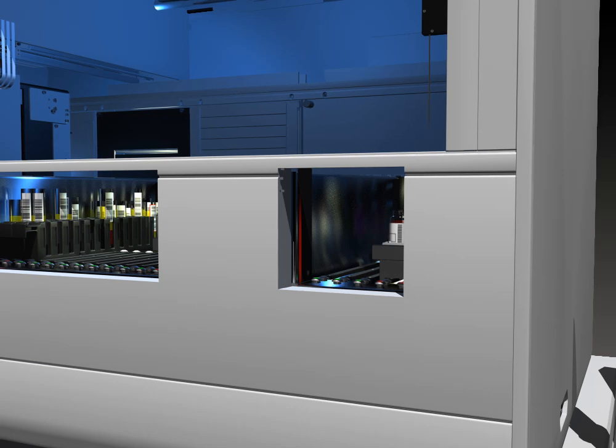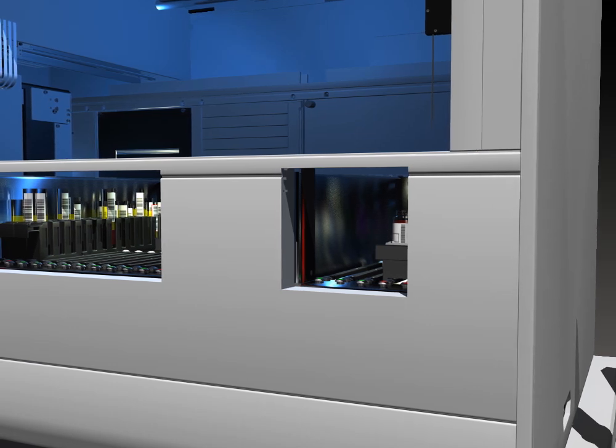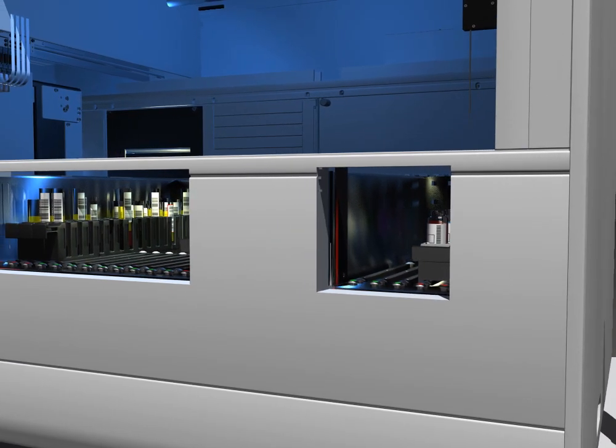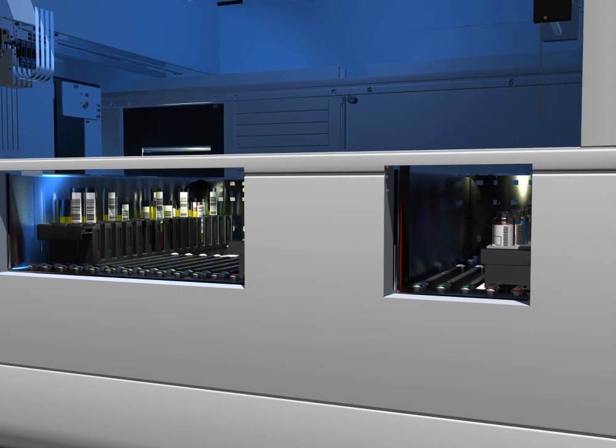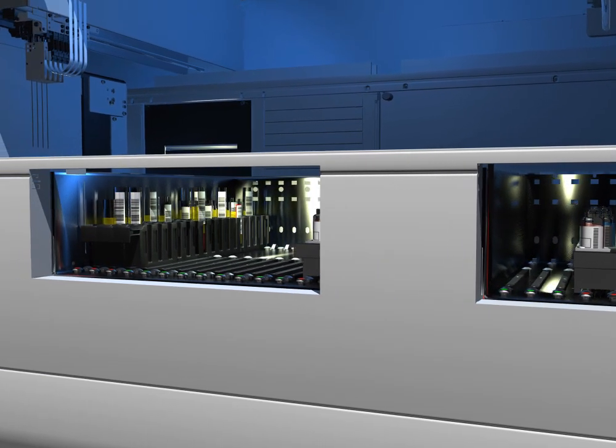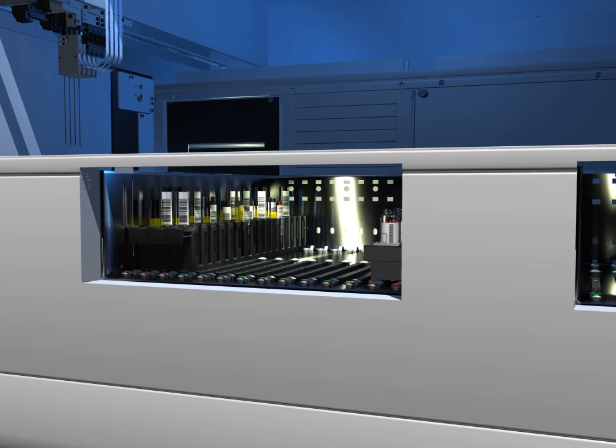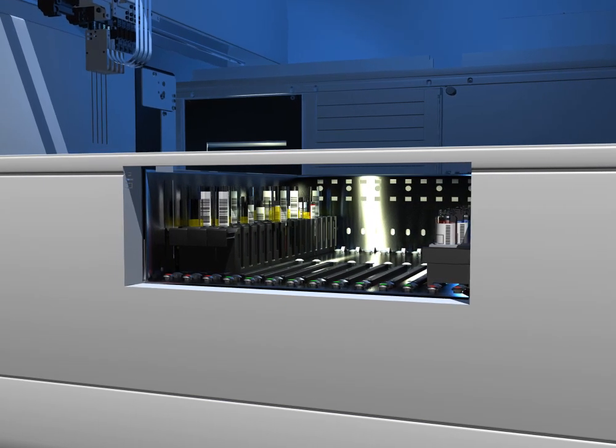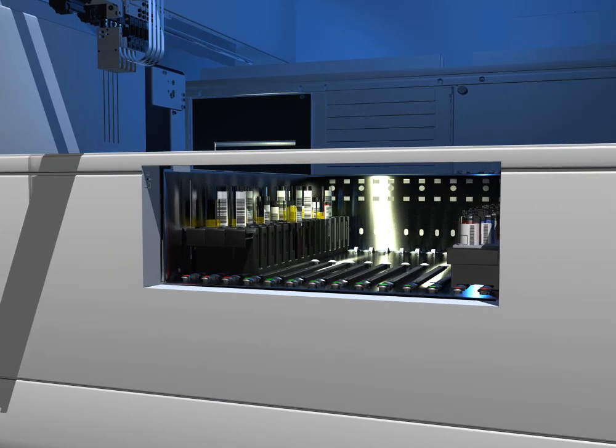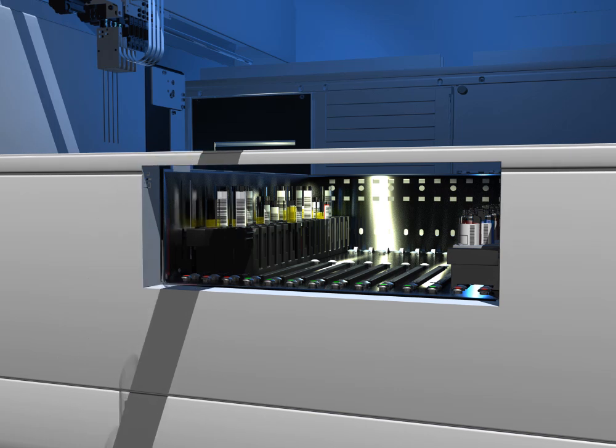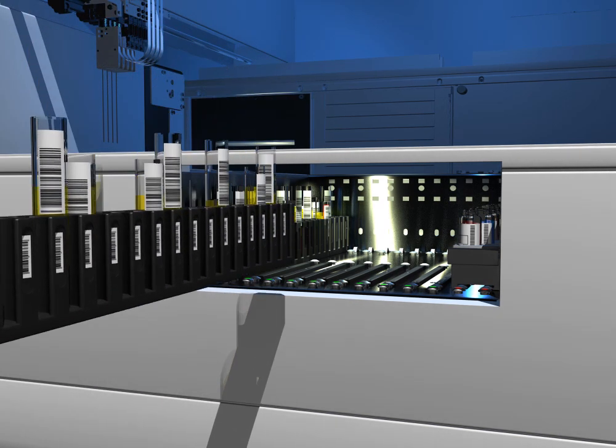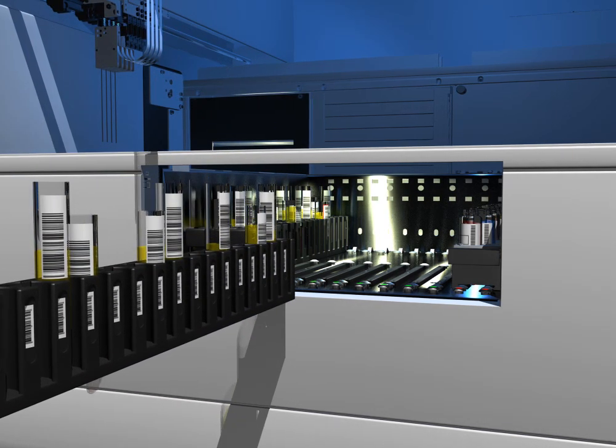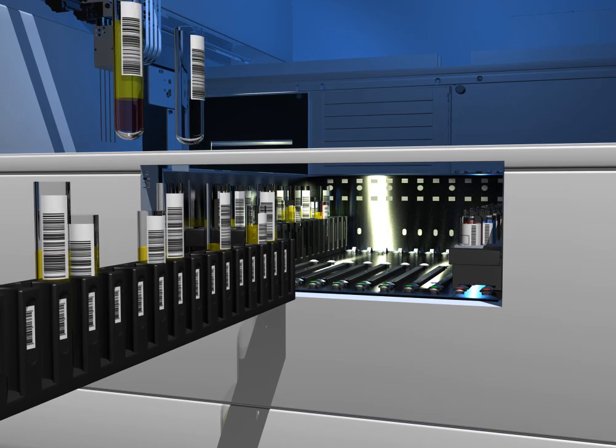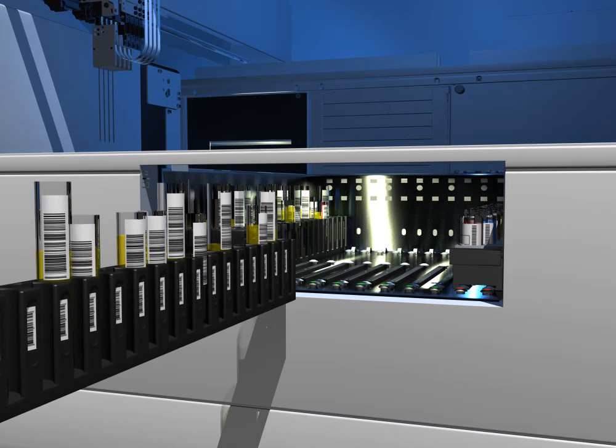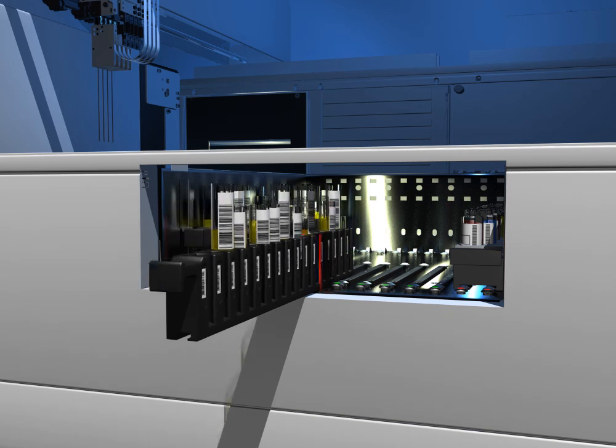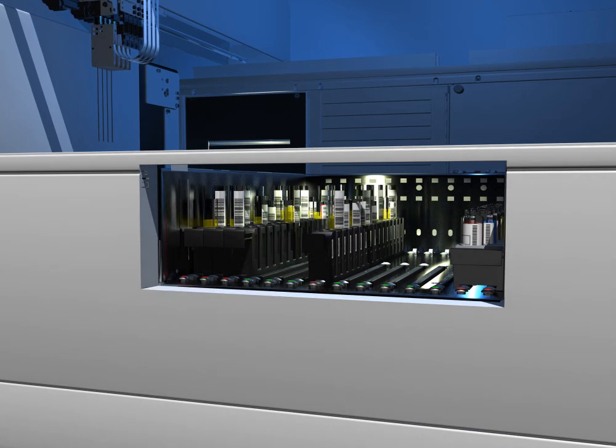Immucor reagents all feature barcodes and can be placed in any position on the reagent rack. Each reagent barcode contains the reagent type, lot number, expiration date, and a unique serial number for every vial, so that Neo can maintain an inventory of onboard reagent volumes. This gives us true positive ID and immediately tells Neo what samples or reagents are loaded in what position. Neo features real-time barcode read, so the instrument is actually reading the barcodes as you slide the rack into the loading bay.